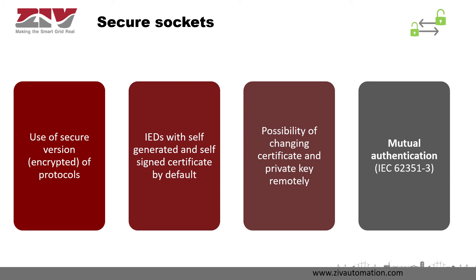Another main cybersecurity feature is securing the communications. The IED uses secure sockets — for example, HTTPS for web, SFTP for file transfer, SSH for remote access to console, or LDAPS or StartTLS for remote authentication. The use of non-secure sockets is also available. The IED is delivered with a self-generated, self-signed certificate by default, but offers the possibility of changing both the certificate and the private key remotely to allow the final client to customize security.